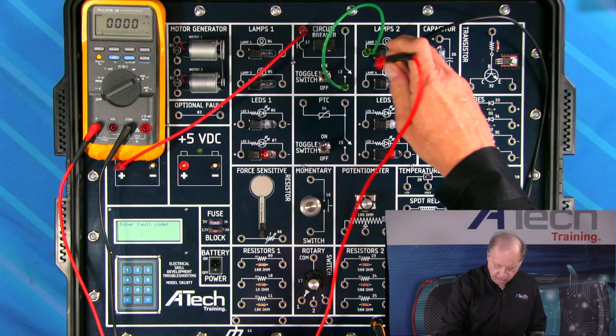So that's 260. I'm going to turn it back off and reconnect my feed side. Now I'll take my black lead to ground here, take my red lead, and put it after my lamp to check the ground side.